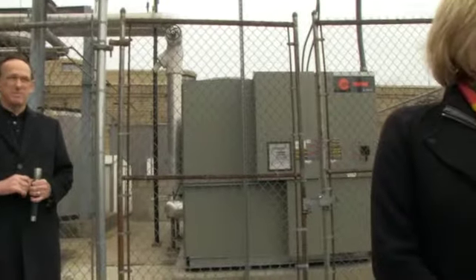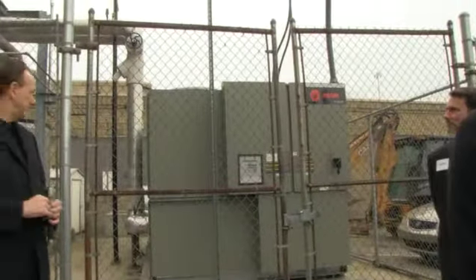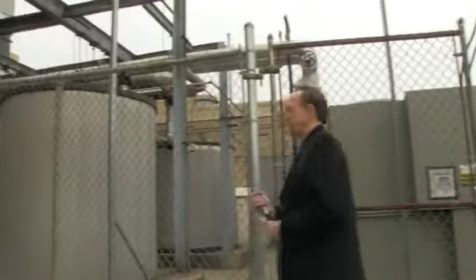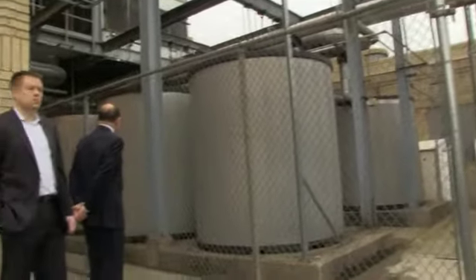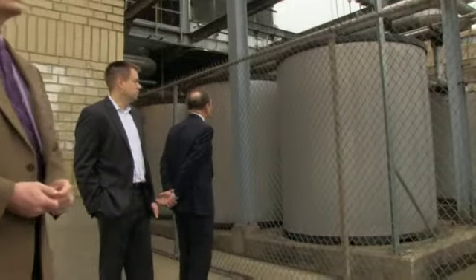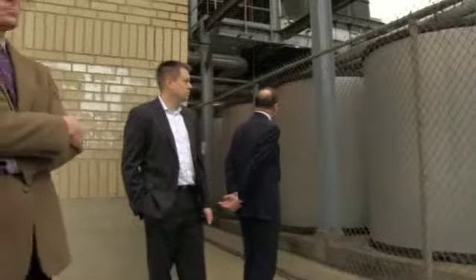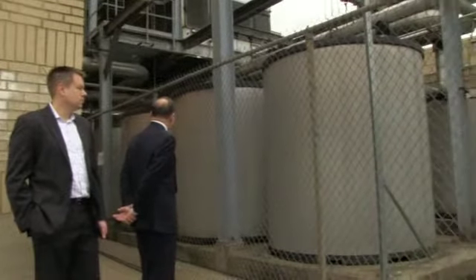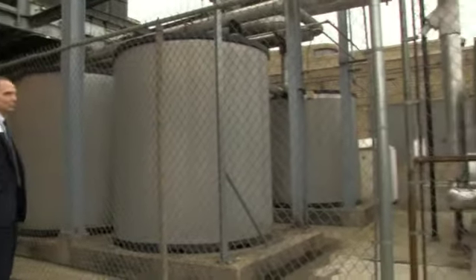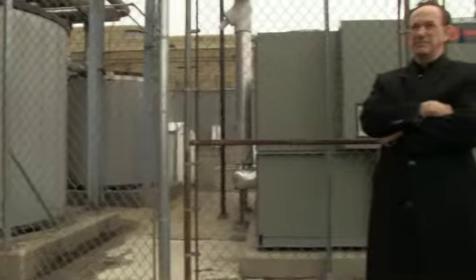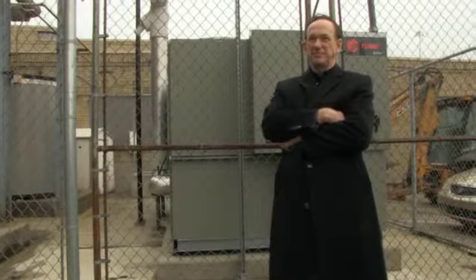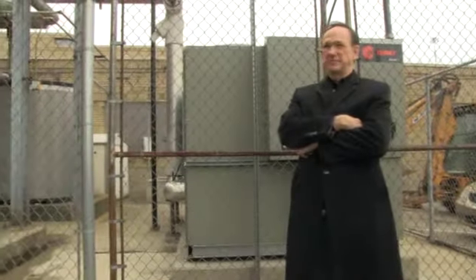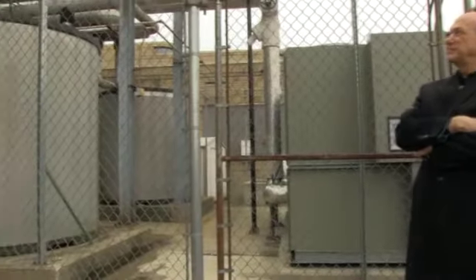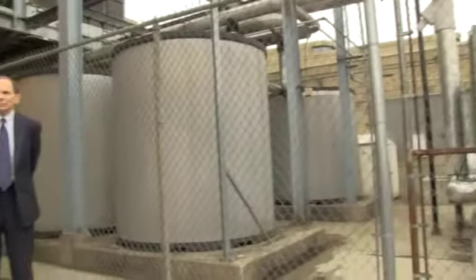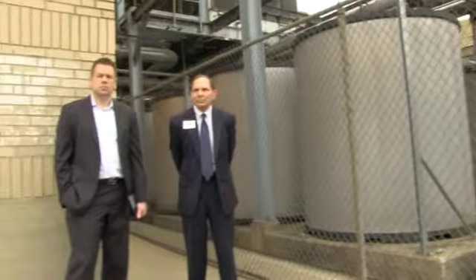And then these tanks that you see right here are what I was referring to as the thermal ice storage system. If you look at the network of pipes, it comes from the chiller, goes into those tanks, then goes back out to the chillers, but there's another series of coils and pipes that go through the inside of that. So the two water systems don't actually mix. You're transferring the cold water that's coming from the chiller to another set of pipes that are going through there that are freezing the ice.